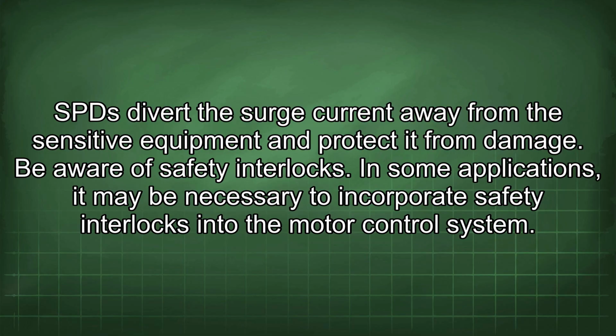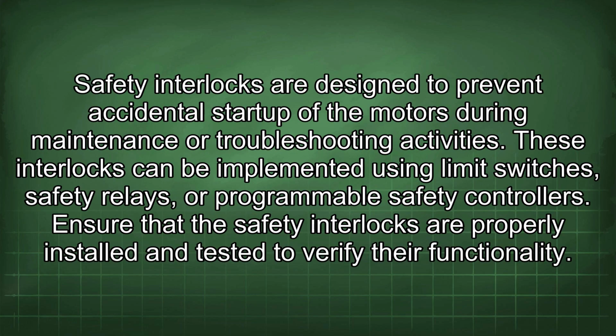Be aware of safety interlocks. In some applications, it may be necessary to incorporate safety interlocks into the motor control system. Safety interlocks are designed to prevent accidental startup of the motors during maintenance or troubleshooting activities. These interlocks can be implemented using limit switches, safety relays, or programmable safety controllers. Ensure that the safety interlocks are properly installed and tested to verify their functionality.